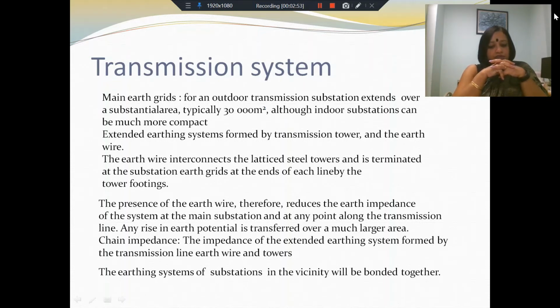Then we have what is called the chain impedance. The chain impedance is the impedance of the extended earthing system formed by the transmission line, earth wire, and towers. So you have the earth, the transmission line, you have the tower footing resistance, and you have the grid earth, the main earth grid, and then you have the chain impedance, which also takes into account the total impedance of the extended earthing system, which comprises every earth object or every earth point that is part of the transmission line.